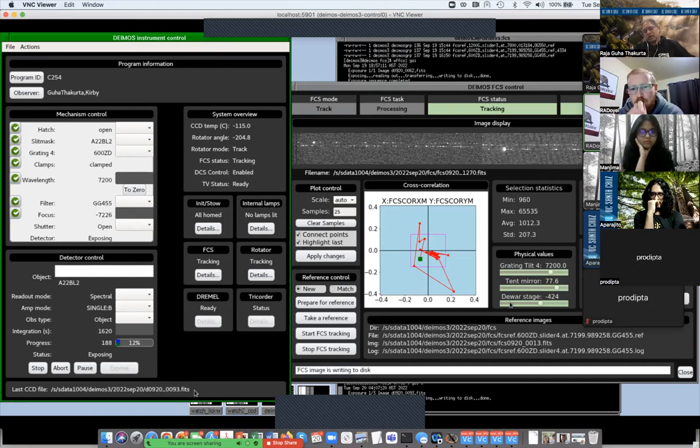The dewar is the flask that holds the liquid nitrogen containing the CCD. That contains a stage in which the CCDs can move relative to the beam of light. Those are the three controls: coarse and fine control in X and Y. It uses all three of those things.